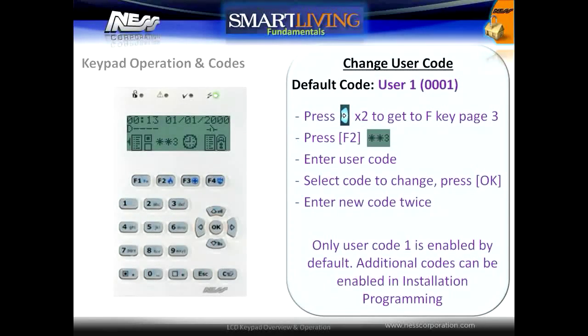To change the user code, press the right arrow key two times to go to shortcut page 3. Press the F2 key, enter in an existing master user code, and select the code to change, then press OK. User code 1 is the only code enabled by default. Additional codes must be enabled in installer programming.